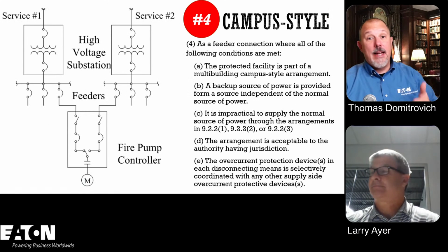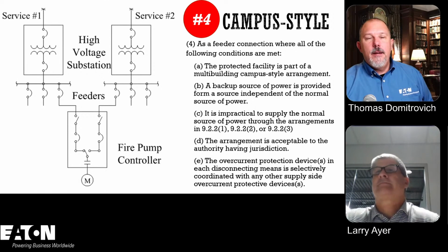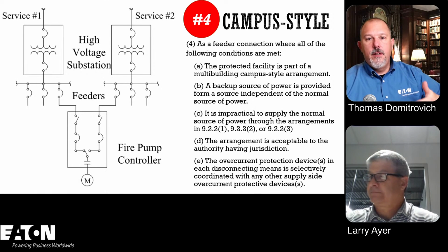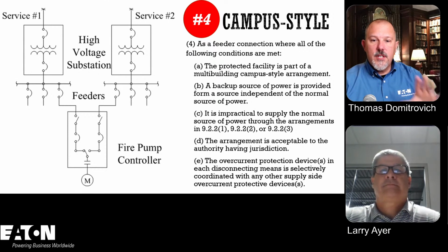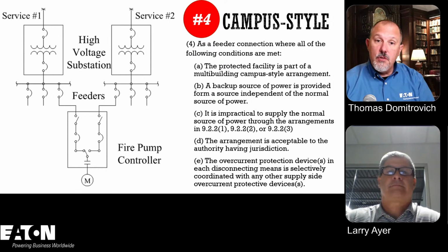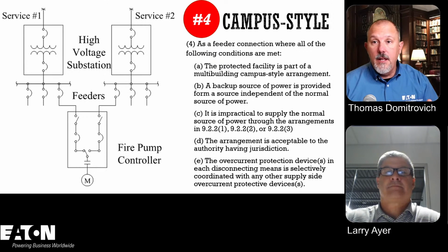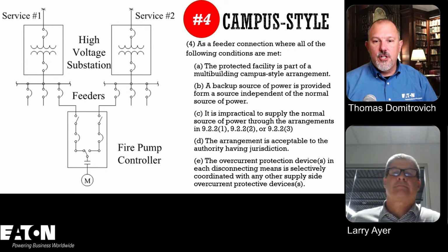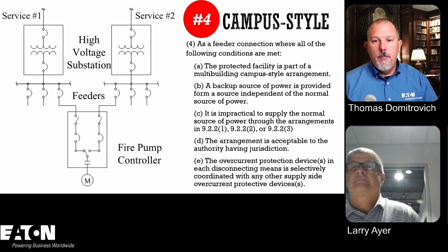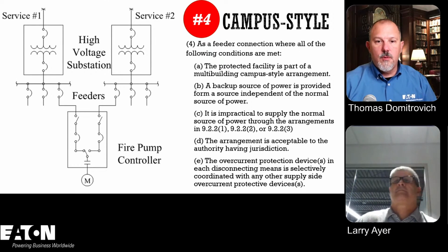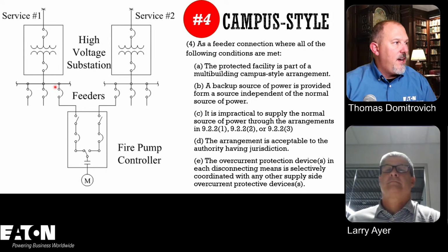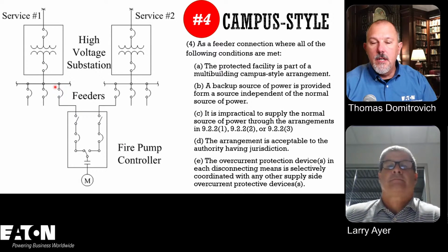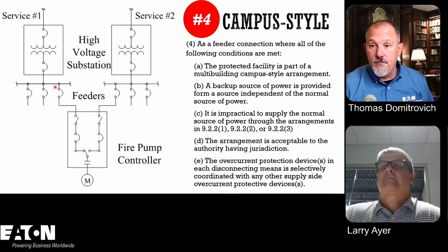Number 4, campus style. So this one always comes up as a confusing point for a lot of people, because when you have a large facility, they want to leverage this campus style option, but there are special considerations with regard to all of these overcurrent devices that you have upstream of that fire pump, and the details can be challenging to get by to make an installation meet all the aspects of this requirement.